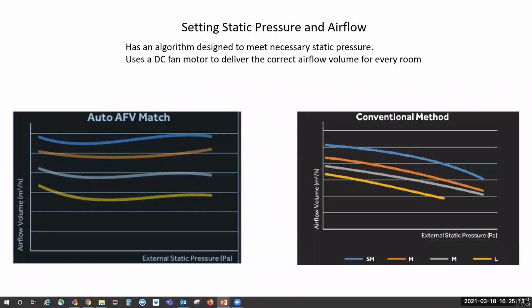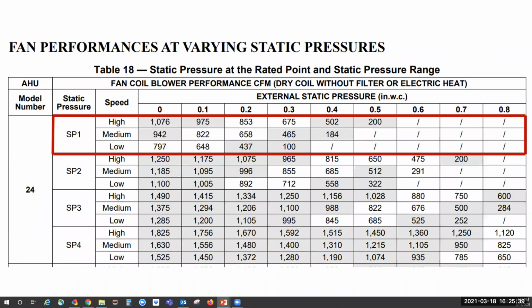Once again, static pressure. You're going to remove that metal panel on the air handler and your little IR receiver, the little white thing there that had the manual button on it. You're going to use the remote control to set this. You cannot use a 24-volt interface to set that. It would have to be done with the wireless remote control. It comes default with the on SP1.